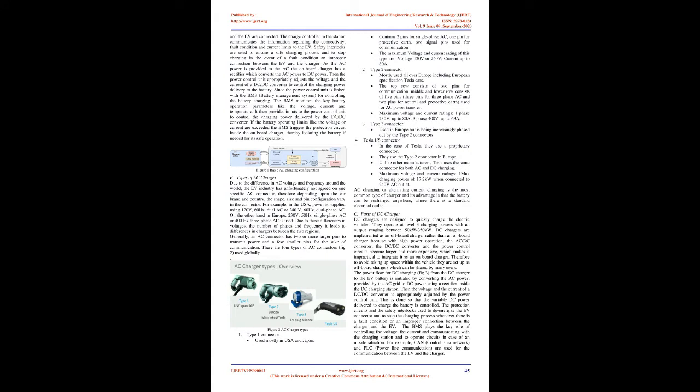Conductive charging - Parts of an AC charger: In its simplest form, AC charging uses an onboard charger to convert electricity from AC power, from the conventional AC grid, to DC power to charge the traction battery. Cars have a standardized vehicle inlet, and a charging cable is used to connect the vehicle connector to the AC charging station. In some cases, the charging cable is permanently connected to the charging station as well, similar to the petrol pump. There should be several essential components in an AC charging station for a safe and reliable charging process. The essential components are shown in the power flow, Figure 1, from the charger to the EV. The moment the charging station and the EV are connected, the charge controller in the station communicates the information regarding the connectivity, fault condition, and current limits to the EV.